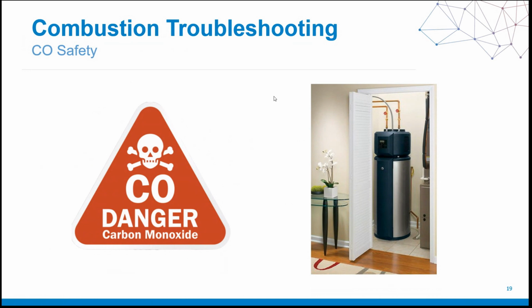For those of you that do not have a personal CO monitor, you should get one. But if you don't, your combustion analyzer has an ambient CO function that a lot of you are not aware that it has. You can actually monitor the CO in the space that you're in and know what the level is, and know the level of safety or the ensured safety of the conditions that you're in.